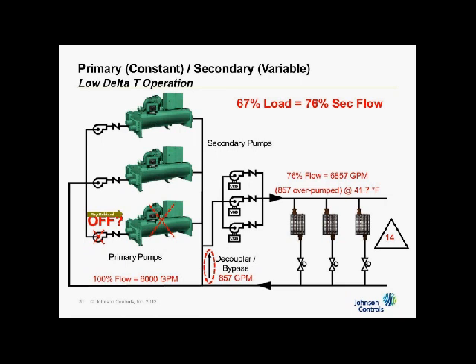But what is bad is if you don't have optimal control and variable speed drives on your condenser water pumps and everything else, and you have all the optimal control going on, then it will cost you more energy. So that's another problem. There's more energy in the plant. Secondarily, I can't load up any of my chillers above, in this case, 87.5%, because the load up capability of the chillers is 14 divided by 16. That ratio of actual delta T to design delta T comes into play, and I can't load up these chillers greater than 87.5 because my formula is load is equal to flow times delta T. My flow can't change because it's a design flow, a constant flow. My delta T is low, so you're just telling the chiller I don't need more than 87.5. The system isn't asking for it, so you can't load the chillers up.